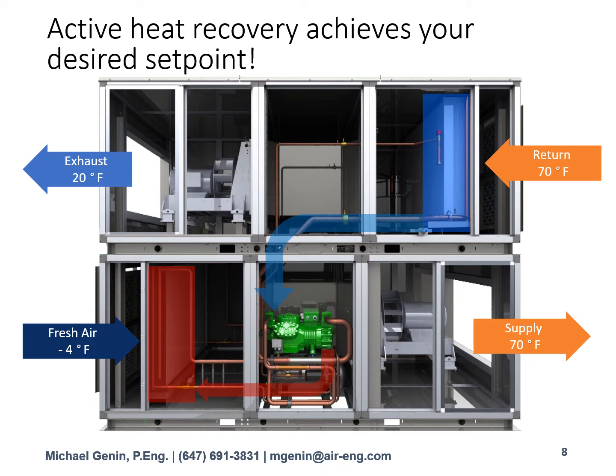And where that stems from is if you look at the exhaust temperature, which in this case is 20 Fahrenheit, our exhaust temperature is still warmer than our outdoor air conditions. So of course it makes more sense to extract heat energy from that exhaust rather than attempting to extract it from the ambient in these conditions.